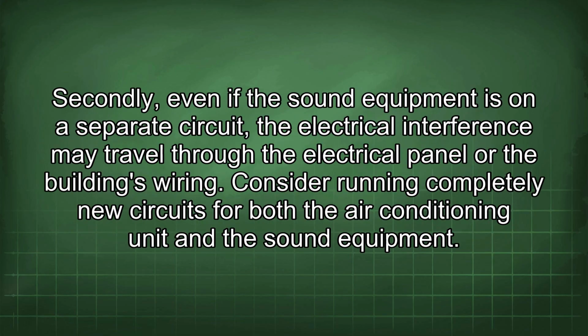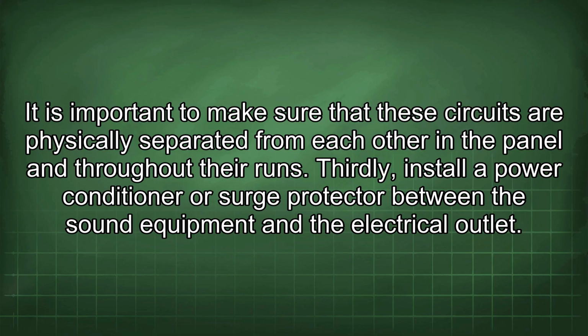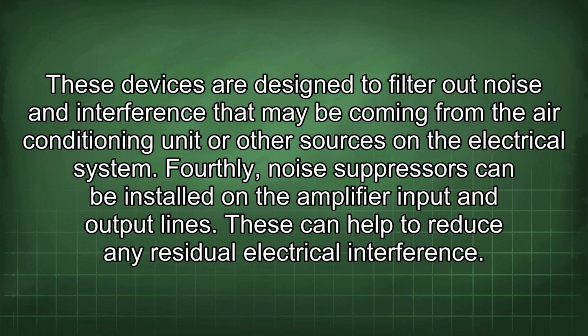Secondly, even if the sound equipment is on a separate circuit, the electrical interference may travel through the electrical panel or the building's wiring. Consider running completely new circuits for both the air conditioning unit and the sound equipment. It is important to make sure that these circuits are physically separated from each other in the panel and throughout their runs. Thirdly, install a power conditioner or surge protector between the sound equipment and the electrical outlet. These devices are designed to filter out noise and interference that may be coming from the air conditioning unit or other sources on the electrical system.